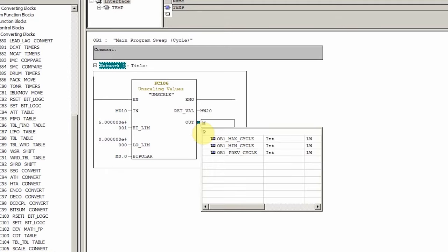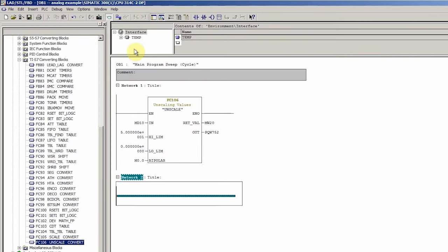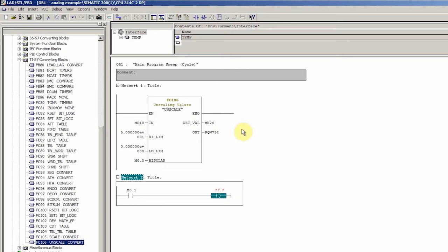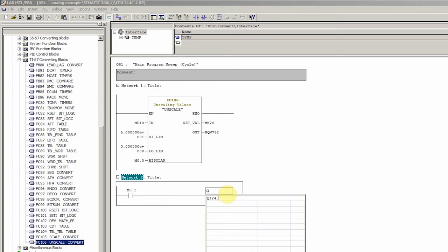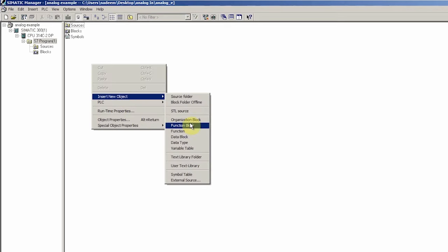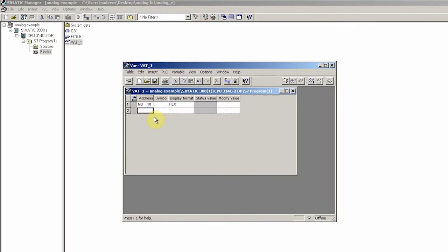Next we will assign memory word MW20 to the return value to show any alarm codes. Next we will assign the output register PQW752 for channel 0. The analog output value will be transferred to channel 0 via output word 752. For the run command of the VFD, we will simply turn on output Q124.0 with memory bit M0.1. Next we will go back to the main project and create a variable table. This variable table will be used to modify register MD10 values for analog output channel 0 and to force on and off run command bit M0.1.